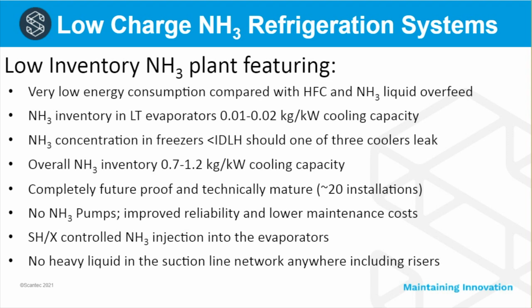Here we see some of the bullet points of centralized low-charge ammonia systems. Just as an introduction, the main features are significantly lower energy consumption, significantly lower ammonia inventory, somewhere between 3 and 5 times lower than conventional liquid overfeed ammonia systems. There are no ammonia overfeed pumps or ammonia circulation pumps. We don't use superheat control. We control the injection into the evaporators by means of a quality sensor. More about that a little bit later on.